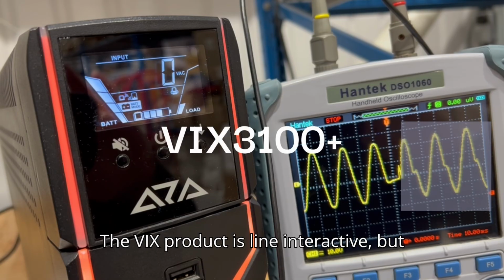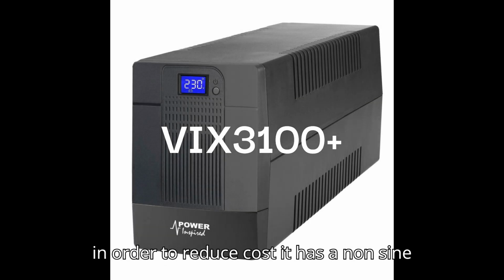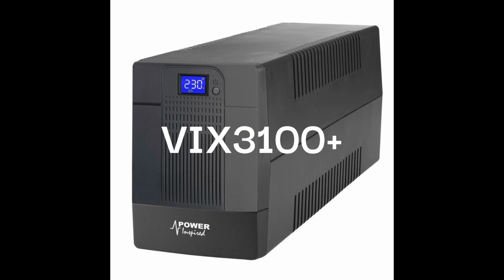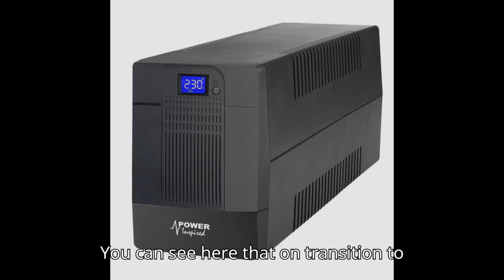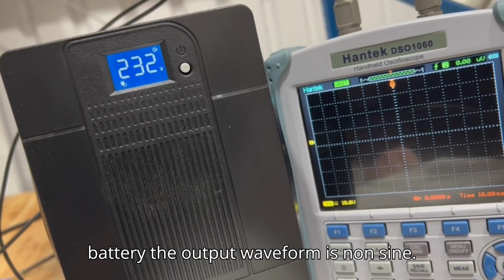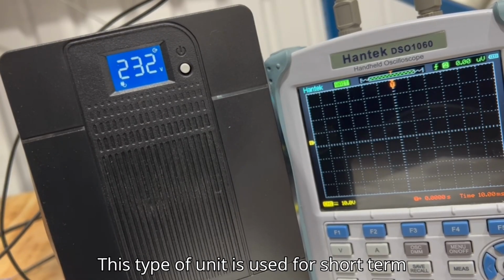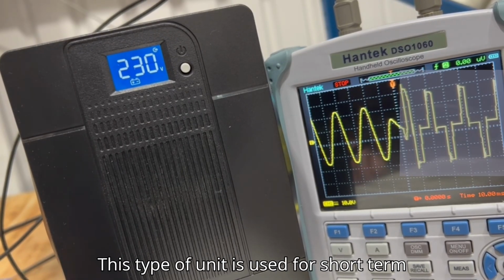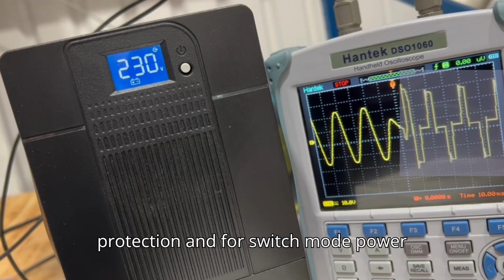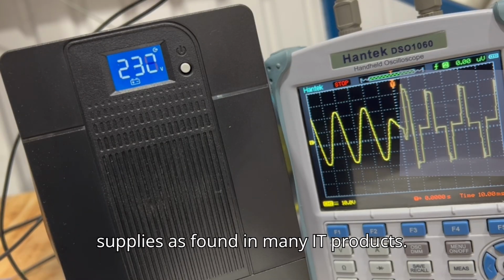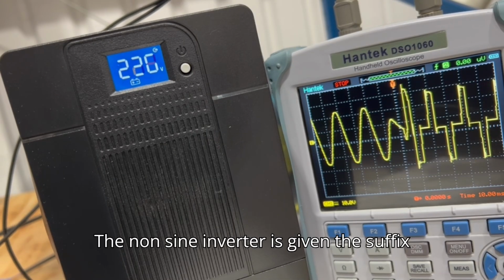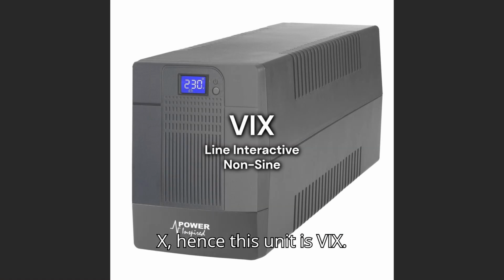The VIX product is line interactive, but in order to reduce cost it has a non-sine waveform. You can see here that on transition to battery the output waveform is non-sine. This type of unit is used for short-term protection and for switch mode power supplies as found in many IT products. The non-sine inverter is given the suffix X, hence this unit is VIX.